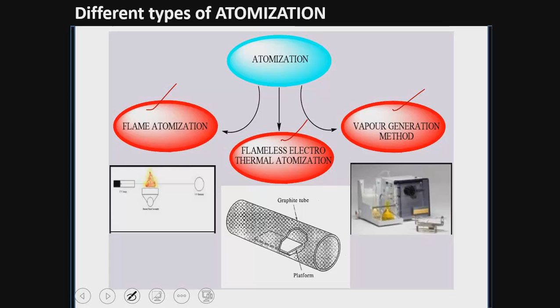The flame atomizers consist of three major components. One is the nebulizer that creates a fine mist of sample solution. Second is the spray chamber where the mist of sample gets mixed with the oxidant and fuel, and this mixture is sprayed inside the flame. Third is the burner that supplies a stable flame to atomize the elements in the specimen. The degree of atomization is temperature dependent, therefore we need a specific fuel oxidant mixture for specific analytes.